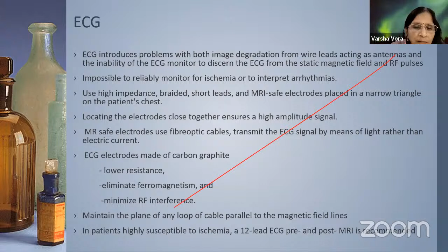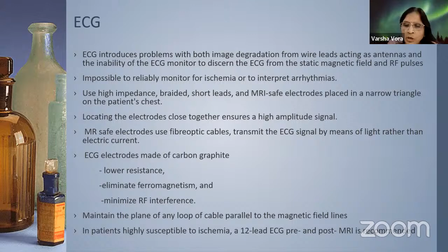Locating the electrodes close together ensures a high amplitude signal. MR safe electrodes use fiber optic cables to transmit the ECG signal by means of light rather than electric current. ECG electrodes made of carbon graphite have lower resistance, eliminate ferromagnetism, and cause minimal RF interference. Maintain the plane of any loop of cable parallel to the magnetic field lines. In patients highly susceptible to ischemia, a 12-lead ECG pre and post MRI is recommended.